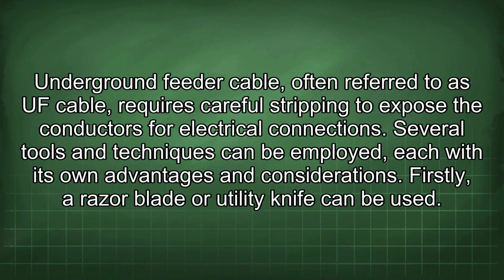Underground feeder cable, often referred to as UF cable, requires careful stripping to expose the conductors for electrical connections. Several tools and techniques can be employed, each with its own advantages and considerations. Firstly, a razor blade or utility knife can be used.